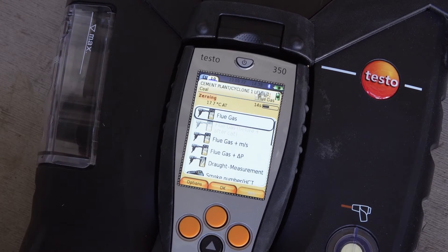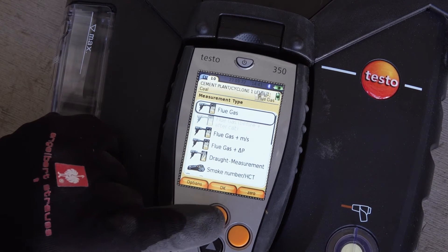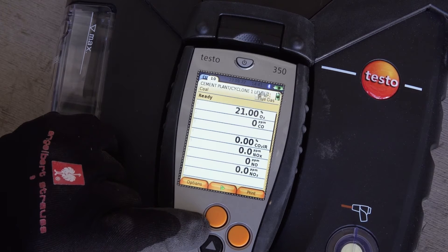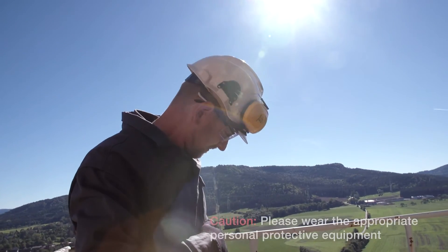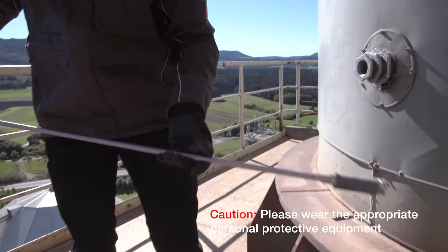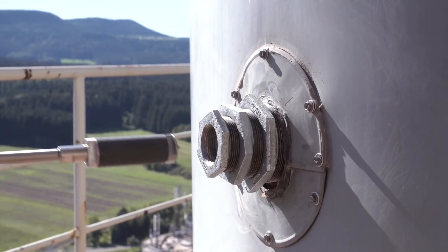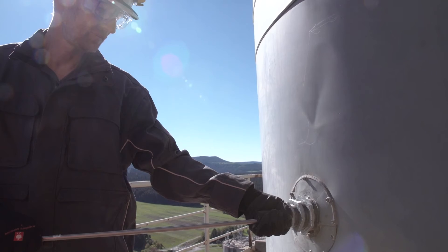Zeroing of the gas sensors is performed before a measurement — the zero point and drift of the sensors are checked, and the O2 value is set to 21 percent O2. Make sure that the ambient air is free of interfering gases such as CO, CO2, or NO during the zeroing phase. The industrial probe with pre-filter used for this measurement is connected directly to the exhaust duct of the plant, with the probe tip positioned in the center of the flue.